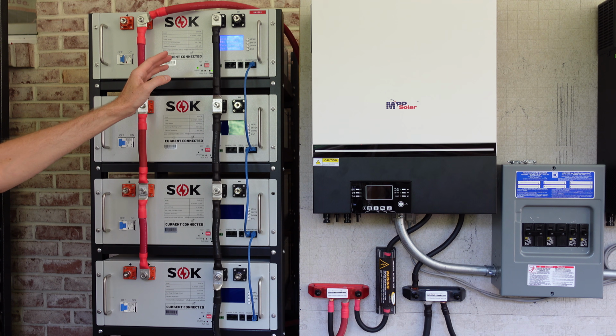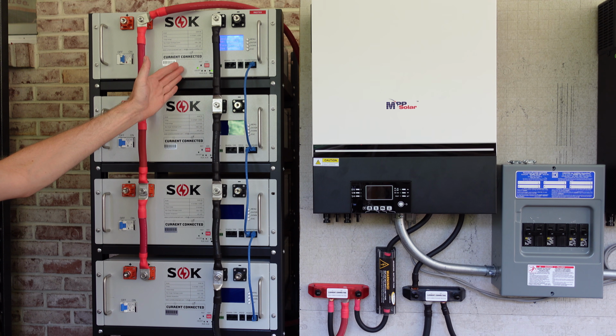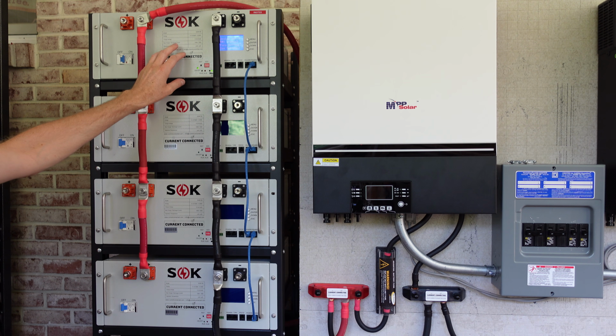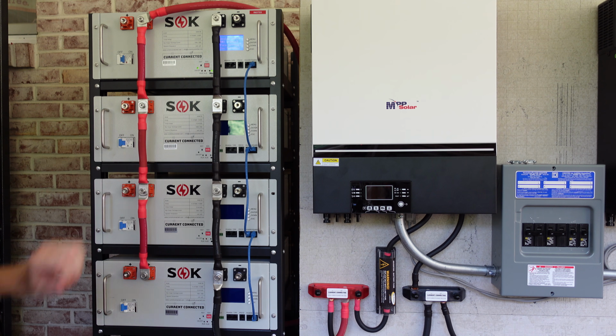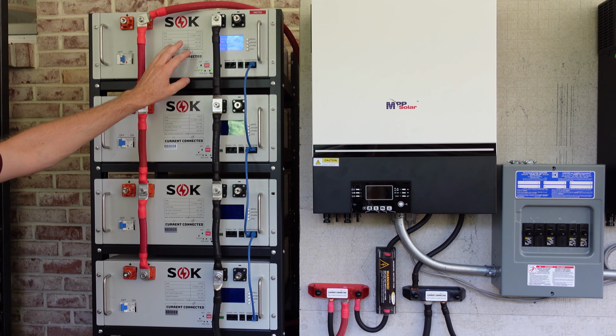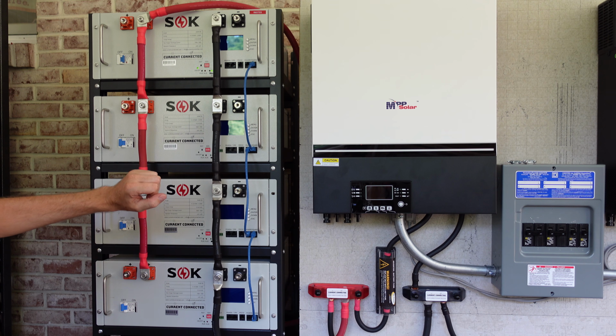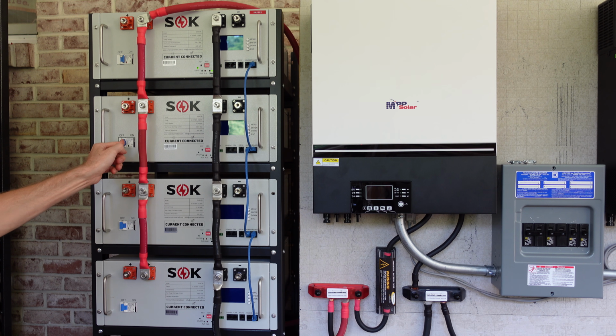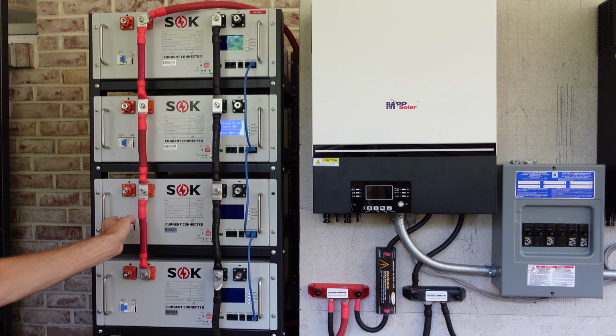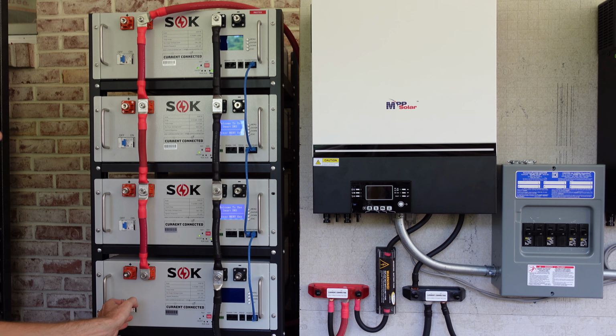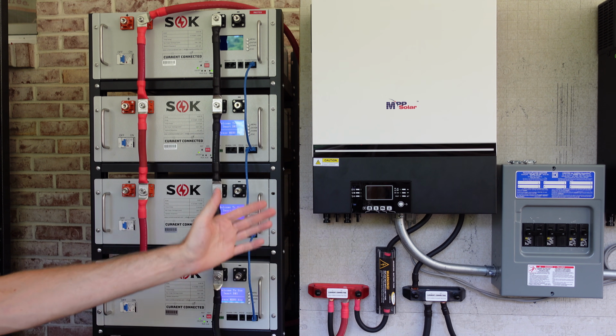So I guess that is how it charges the capacitors up. That's a bit different than I would have expected. That's not how the EG4 batteries work. However, this does not have a pre-charge circuit in like the EG4 battery does. Now that we've confirmed this battery is started up correctly and is not in the alarm state, we're going to go ahead and turn on the remaining 3 batteries and allow those to start up individually. And now that those are started up, we're ready to try out the inverters.